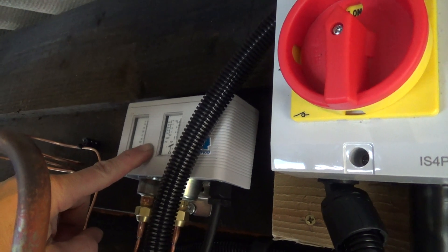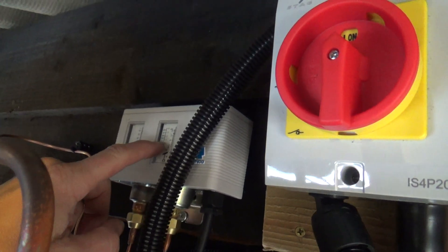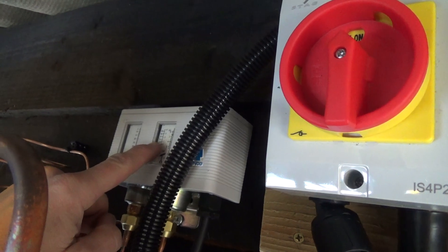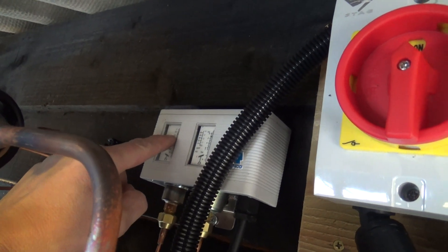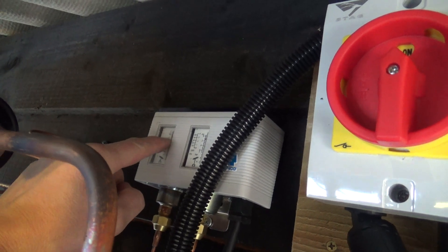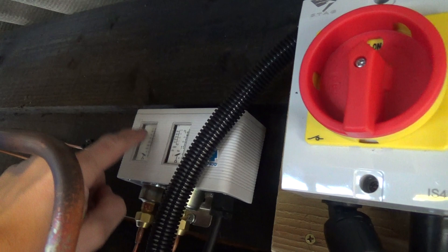This is an LP switch. We've got that set cutting around 15, cut out around 5 I think it is. That scale's not reading very accurately. And the high side one doesn't. It's about 2 or 3 bar. I'll pull your 50 psi out from what it says on there to where it actually trips.